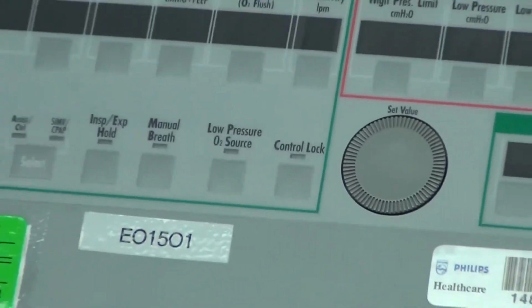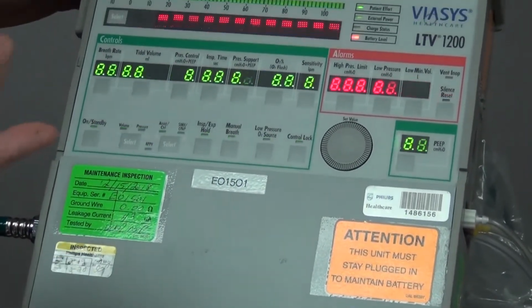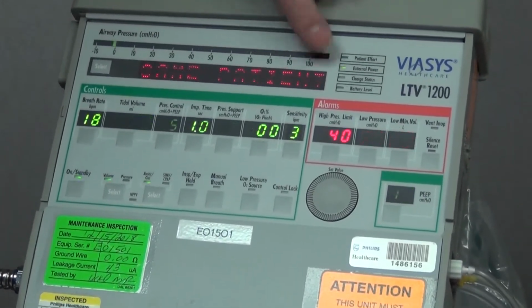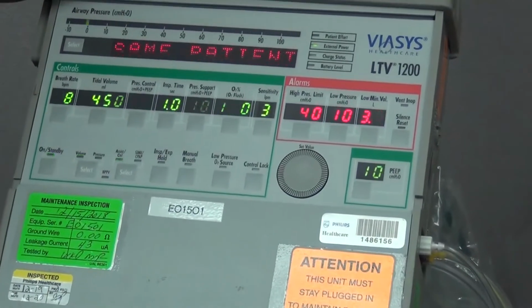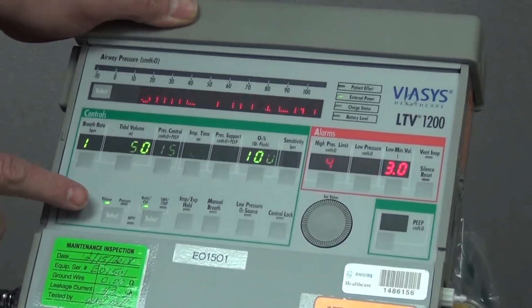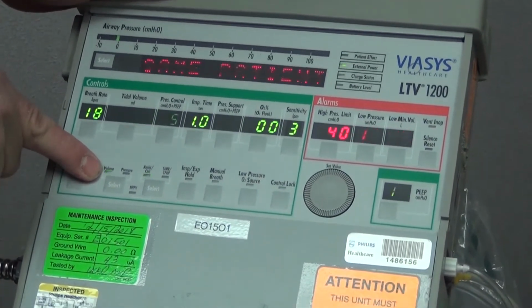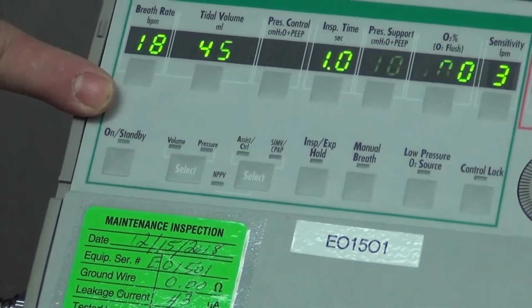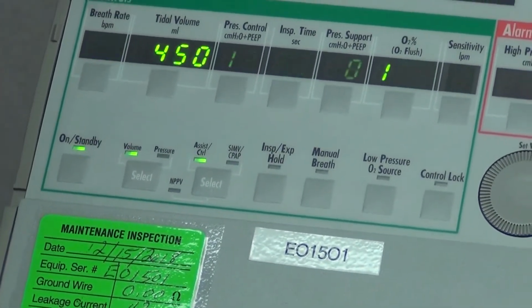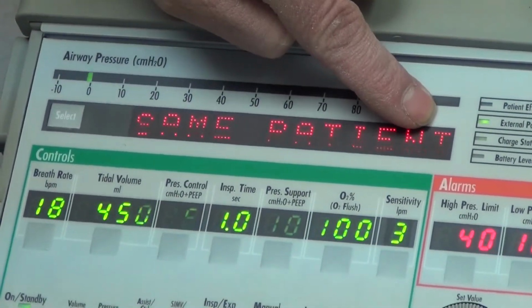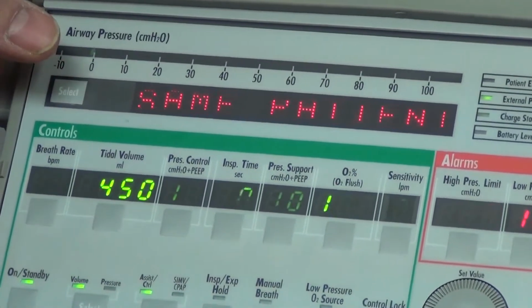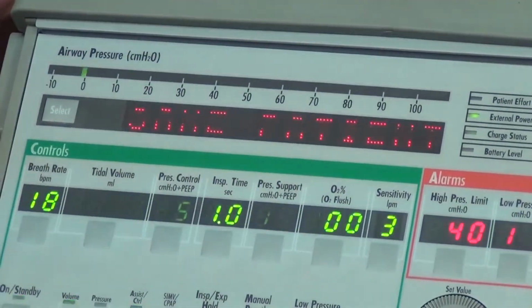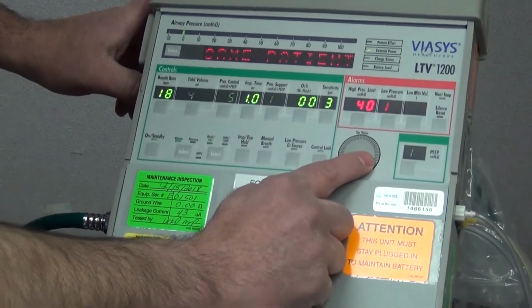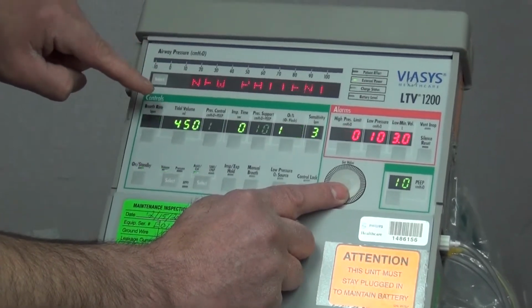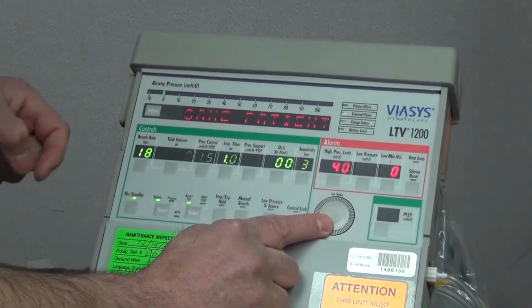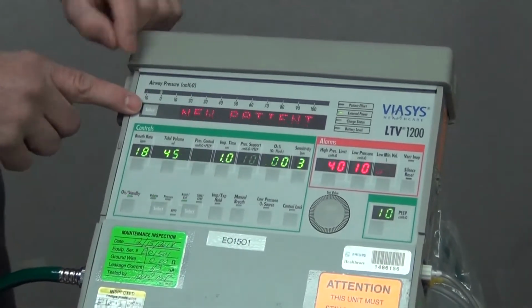So let's go ahead and turn it on. As you turn it on, you can hear the beeping. It's very loud. You have messages at the top, and you have previous settings that the machine was on. Notice that the on is lit up, the volume is lit up, and the assist control is lit up. Let's look at our message board at the top. Notice it says same patient. For our purposes, we're going to say we're using a new patient. To be able to change this, we have to use this little wheel right here. And as you turn it, it either says new patient or same patient. So we're going to go to new patient, and we're going to hit this select button right here.